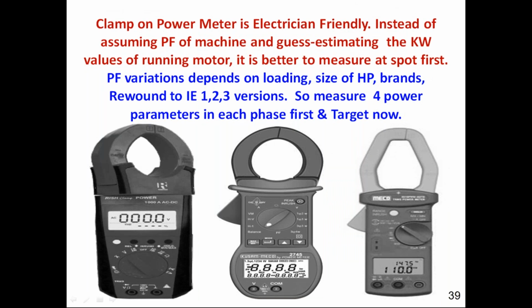This can be used on all the LT services where it is a single clamp-on CT only, and it costs only 10,000 or 15,000, and this can give a lot of inputs to the industry to monitor the instantaneous parameters, especially to the bottom level electrician for the given industry. They can have multiples of these clamp-on power meters instead of clamp-on ammeters, because the industry talks about only amperes. If they talk about kilowatt, kVA, kVAR and PF, they will definitely improve their electrical health in an excellent way. Next, please.